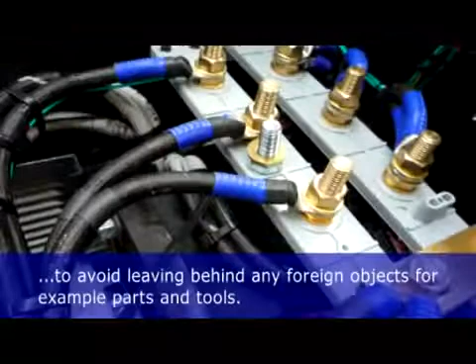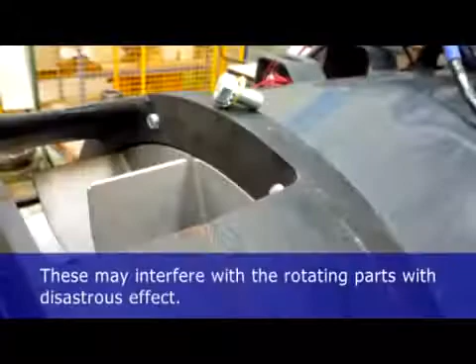Steps should be taken to consider this both in the installation and in the insulation protection system specified at the time of order. This is shown in a separate video. Special consideration must be taken also with the degree of IP protection specified for the machine and the selection of anti-condensation heaters. Care is to be taken whenever accessing the interior of the alternator to avoid leaving behind any foreign objects, for example parts or tools. These may interfere with the rotating parts with disastrous effect.